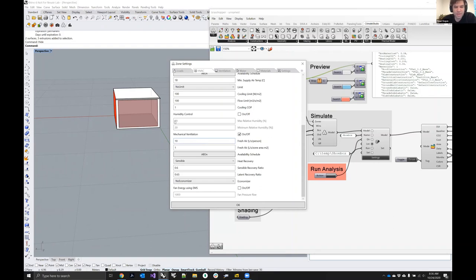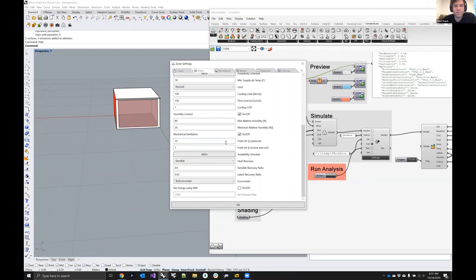Especially relevant for the Indian climate is humidity control — there is a humidistat available to dehumidify or humidify outdoor air going into the zone. There is also a mechanical ventilation component where you can set minimum required fresh air rates per person and per area of program, following ASHRAE guidelines. There's an availability schedule for this too, and you can add heat recovery systems and economizer systems.